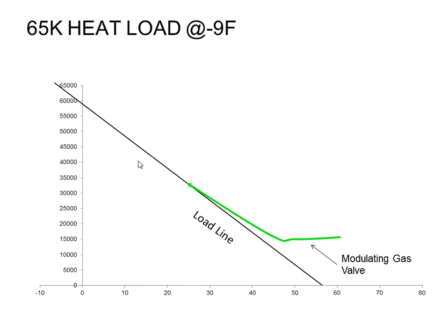There's only 3 times that we'll actually cycle it off. The first is whenever we get so warm outside that we don't need the furnace on anymore, or it's less than 40% capacity. So in this guy's house, once again, 48 degrees or whatever, we'll have to cycle the furnace off. The second time is if somebody walks up to the thermostat and changes the set point.